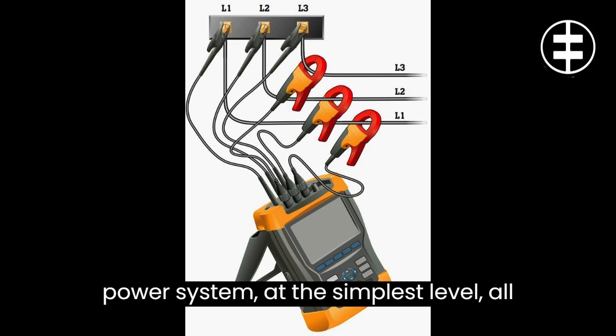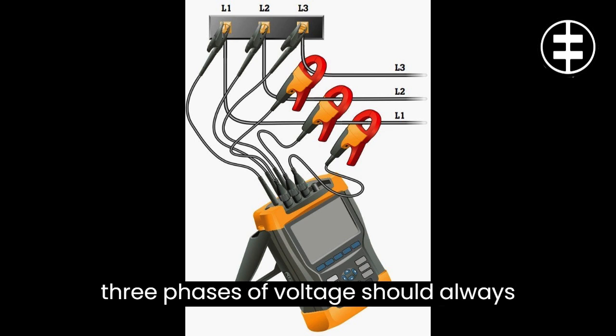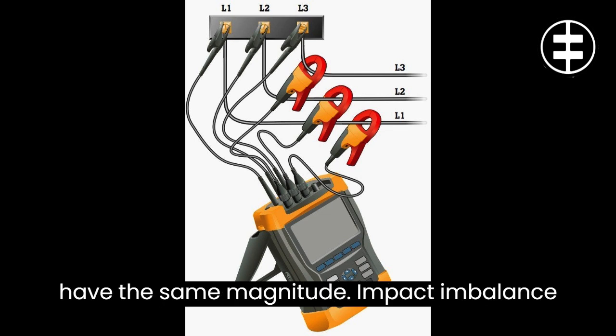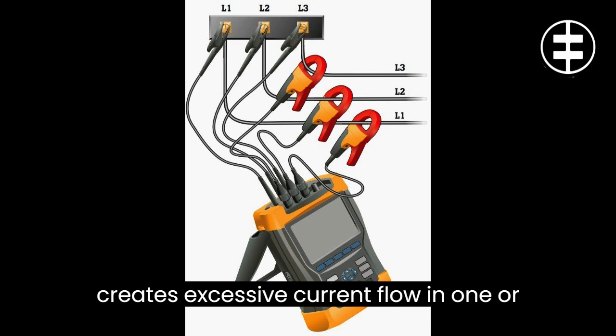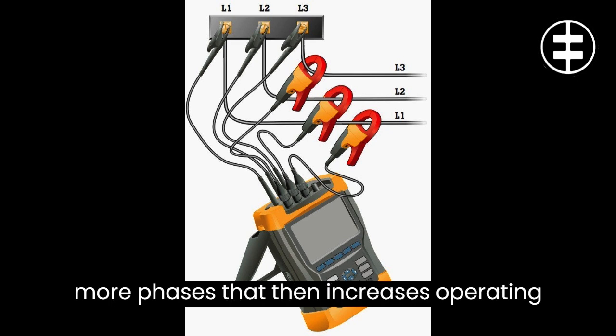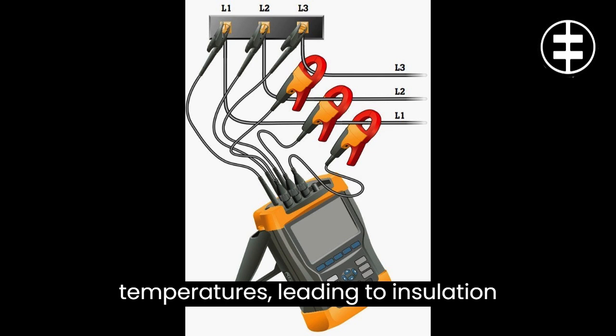At the simplest level, all three phases of voltage should always have the same magnitude. Impact. Imbalance creates excessive current flow in one or more phases that then increases operating temperatures, leading to insulation breakdown.